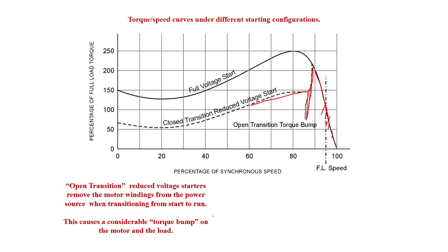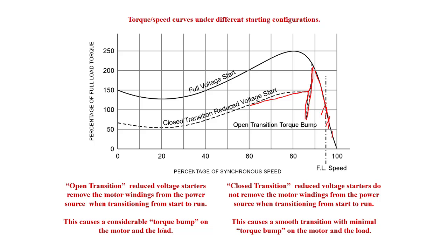So open transition, once again, reduced voltage starters remove the motor winding from the power source when transitioning from start to run, which causes a considerable torque bump, whereas closed transition reduced voltage starters do not remove the motor winding from the power source when transitioning from start to run, and this causes a smoother transition with minimal torque bump on the motor and the load.